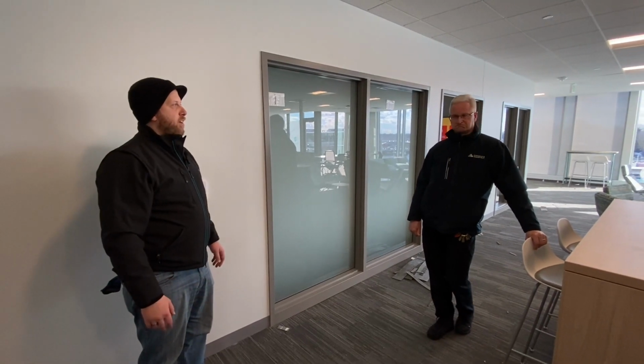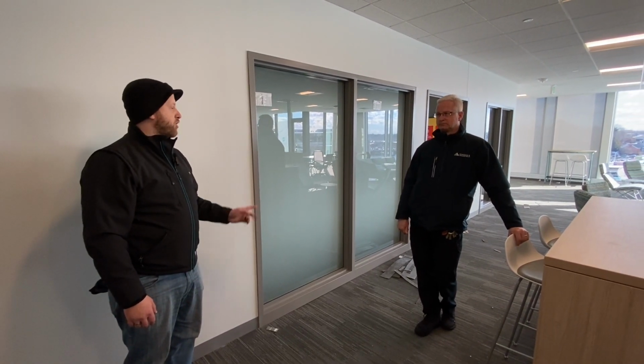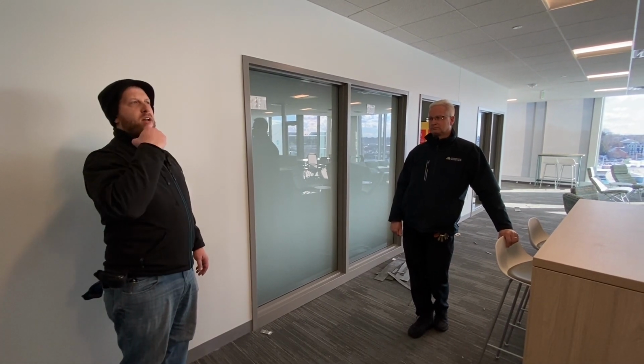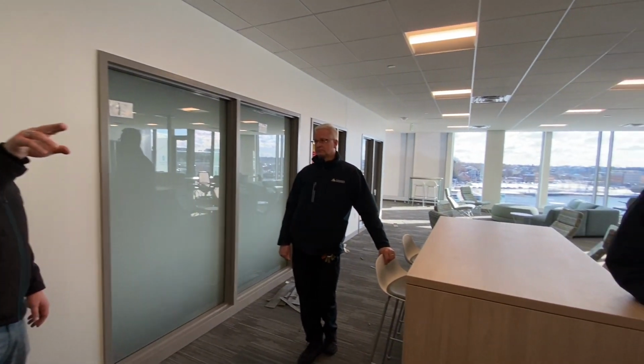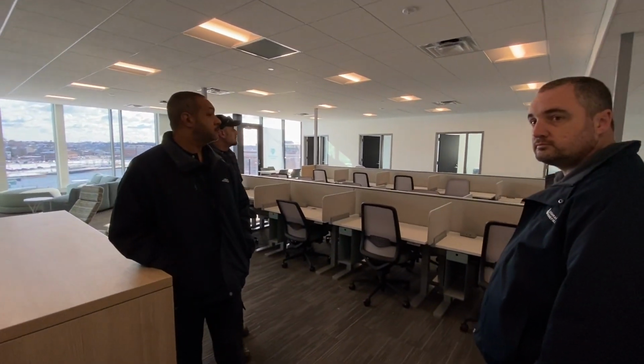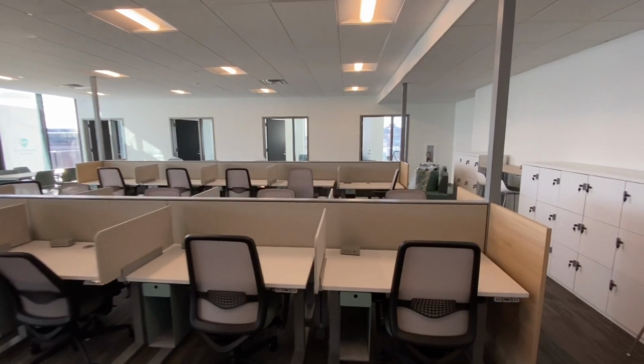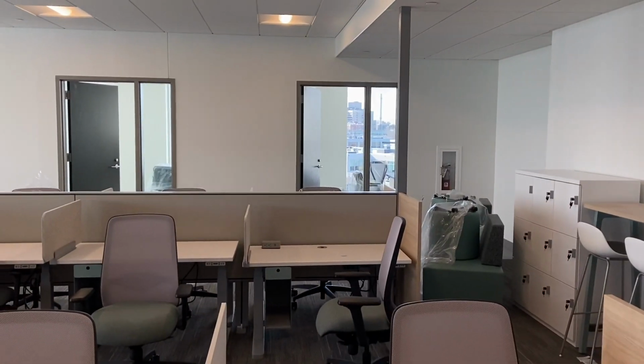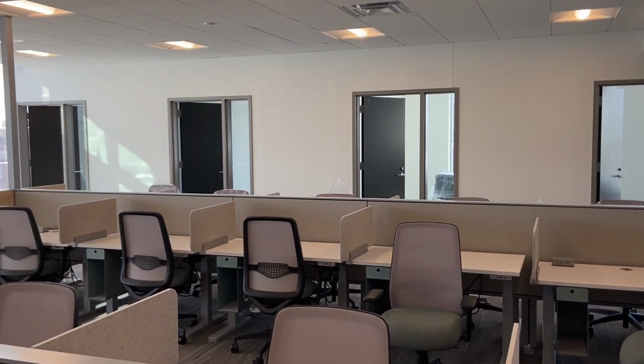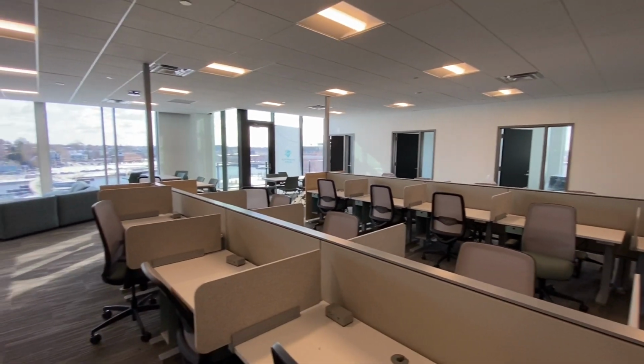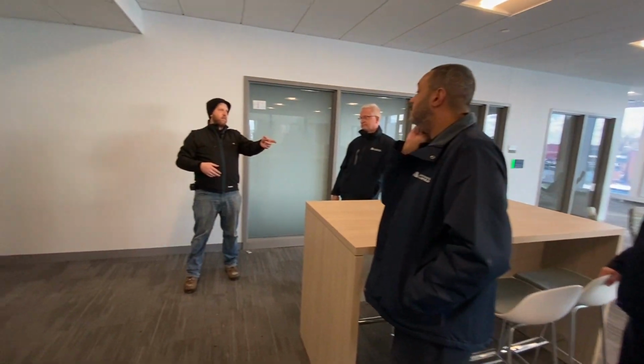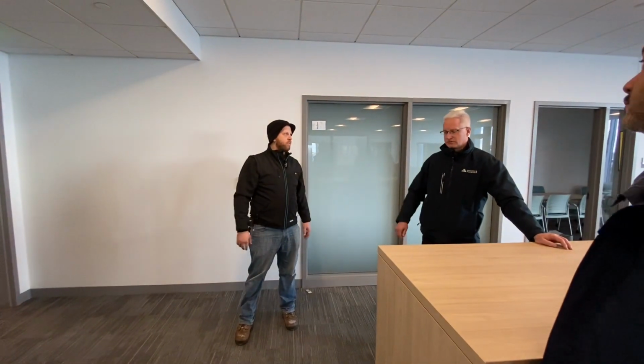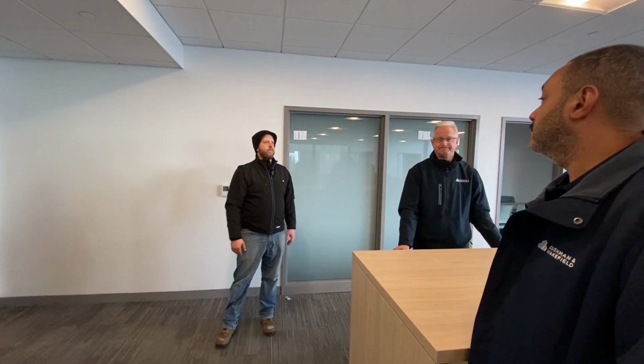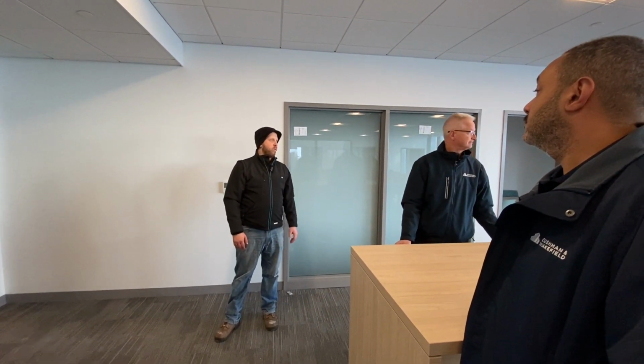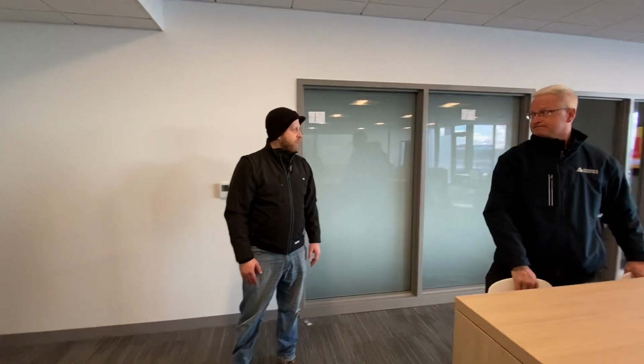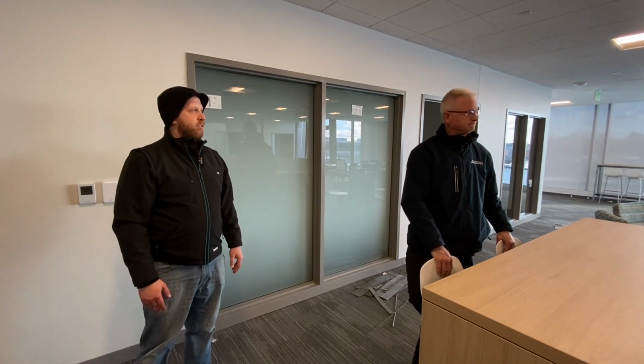Any questions about a VAV box? Pretty standard. There's a bunch of those. The only other concern with these strings of offices is that they may be served by one VAV. So you'll have a thermostat in one office, and if somebody's having a meeting, with 3 bodies in there talking for 3 hours, but the thermostat's in an empty office, they may start getting hot, and meanwhile it's satisfied in the other room. Just typical. Yep, that's typical. So there's a concern, just be aware of that. I think that's pretty much it. Any questions about VAV boxes?